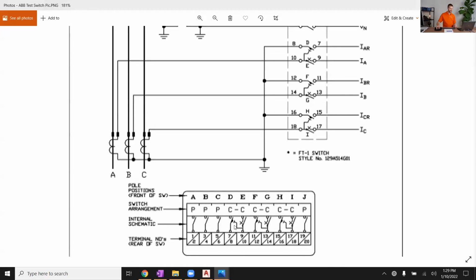This is a little different than the one I configured earlier. It looks like this has currents in the middle. But if A was D and E fingers, you would open up D and then you'd open up E. And at that point, A phase has been isolated from the back of your relay from the real power system. Typically, you wouldn't do just one phase, but maybe in a SCADA checkout situation you might; you'd probably just inject them from your test set. You would typically open all of them fairly quickly. I don't know if I'm answering your question there.